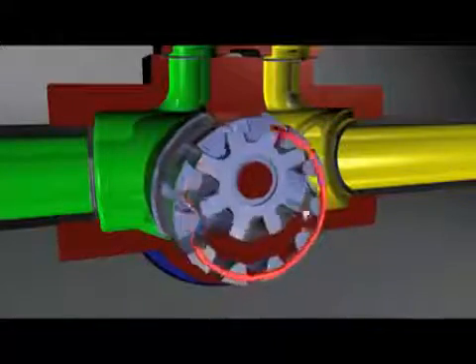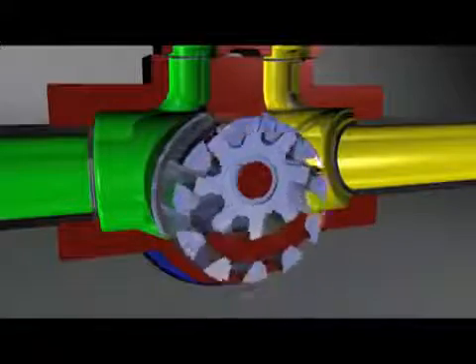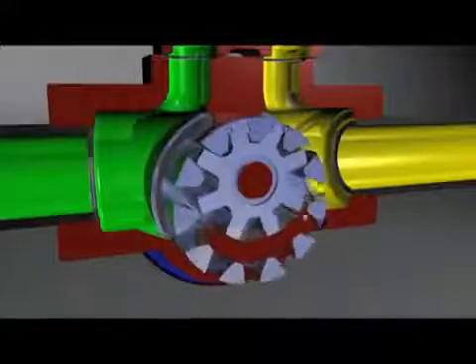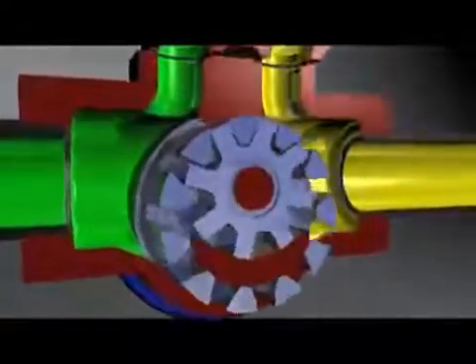Each time the pump completes a revolution, a definite amount of fluid passes from the suction side to the discharge side of the pump. As the rotor and idler rotate, the fluid is prevented from returning to the suction side by the crescent located on the head of the pump, which seals the area where the teeth are out of mesh.